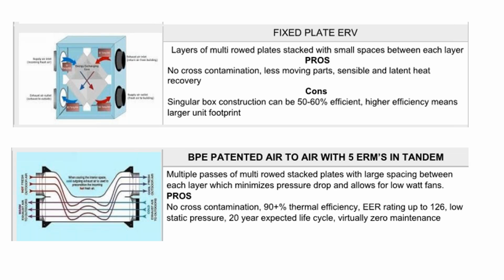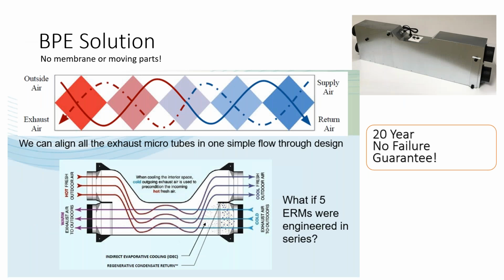We rep a company called BPE, which takes 5 of these units and puts them in tandem. There are multiple passes in each one in the stack plate, and there's a lot larger spacing, so we can have lower pressure drop across it. And also, there's no cross-contamination. We have 90+% thermal efficiency ratings and EER ratings up to 126. So it sounds like a miracle, right? Low static pressure and a 20-year expected life cycle with virtually no maintenance other than on the fans.